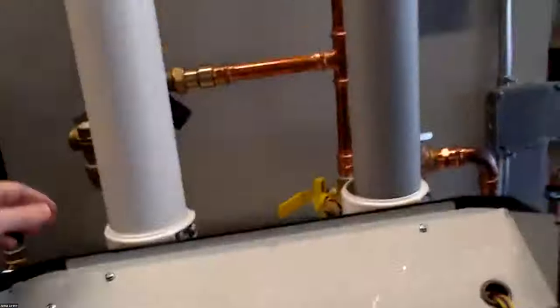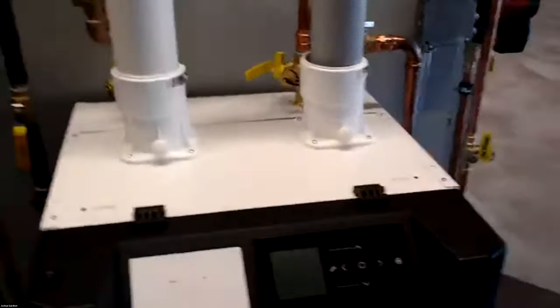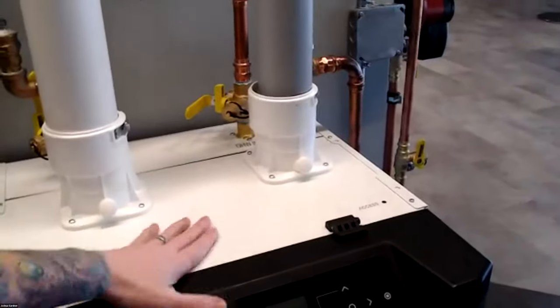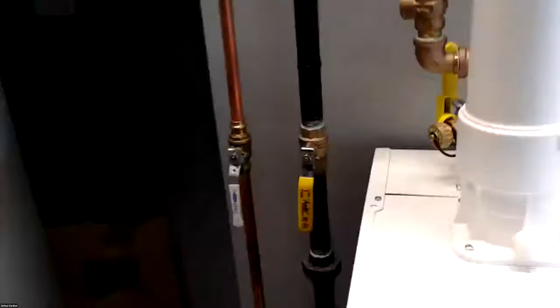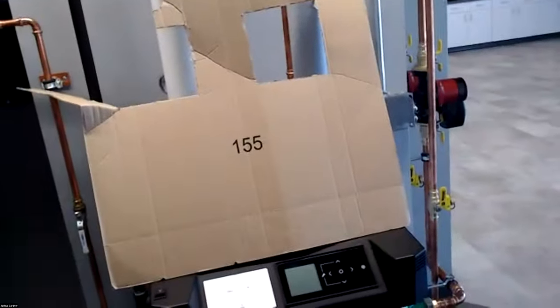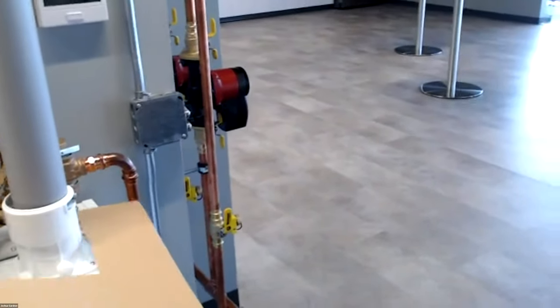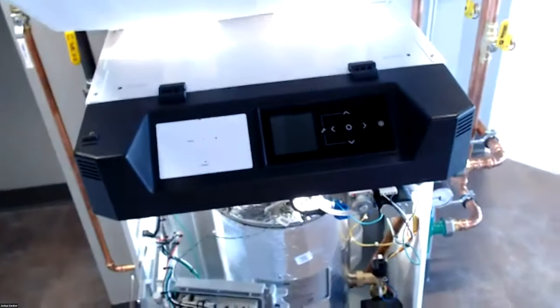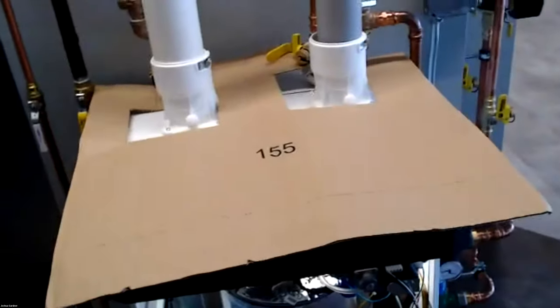Also with this floor boiler, one thing to note during the install, this looks like a great workstation. We include cardboard in the box. And on that cardboard, it's labeled 155 and 199. We give you a top piece that you can cut out and put over this boiler for a workstation. You can work on that and not worry about scratching it up and scratching that control and display. So if you're doing the floor boilers, please use this. That'll keep everything nice and clean for you. And then just take it, you're done, toss it.